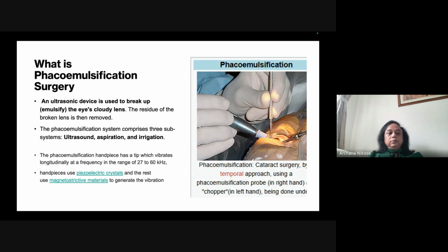Now, as you can see, this phacoemulsification machine is an ultrasonic device. You can see here, this is the phacoemulsification probe. We require both hands. In one hand we use the probe, in the other hand we have another instrument here. It removes the cloudy lens, which is called cataract, from the eye by emulsifying it, and then it is aspirated and irrigated. Now, some physics part of it: the phacoemulsification handpiece has a tip which vibrates longitudinally at a frequency of 27 to 60 kilohertz. And the handpiece has piezoelectric crystals and some magnetostrictive materials to generate this vibration.